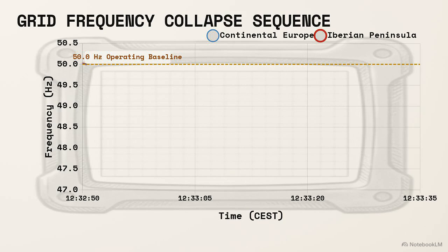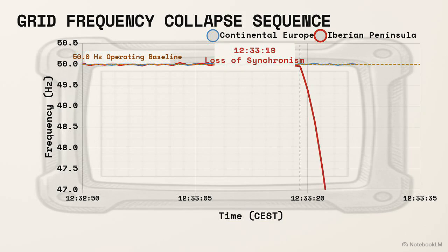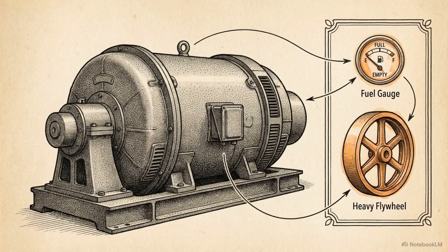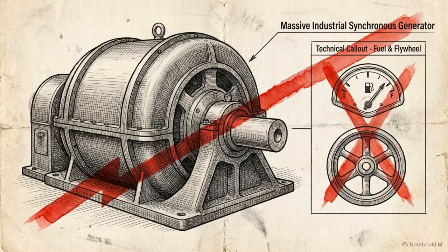This chart plots the frequency of the Iberian grid against the rest of continental Europe. At exactly 12:33 and 19 seconds, the lines violently diverge. This is the precise moment the Iberian grid decoupled from the rest of the continent. Major grid failures are usually assumed to result from a lack of generation adequacy or a deficit of physical inertia. The data shows that neither of those conditions caused this collapse.